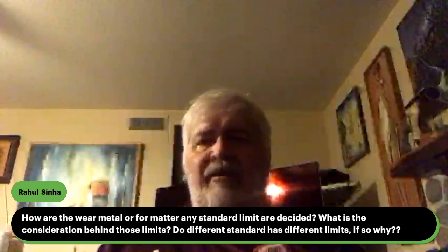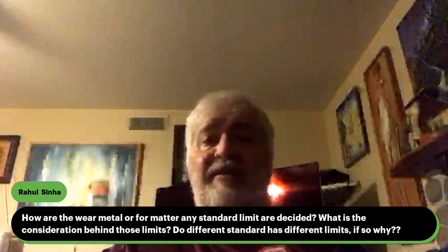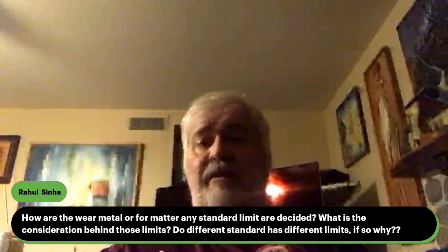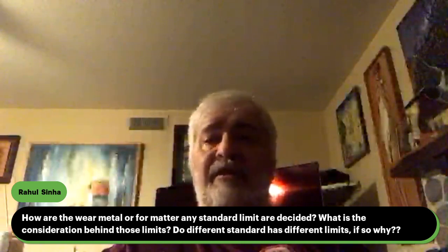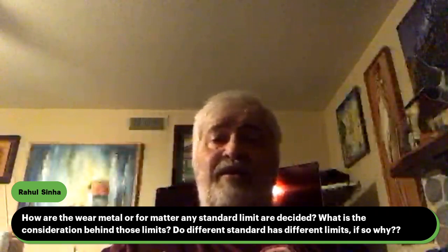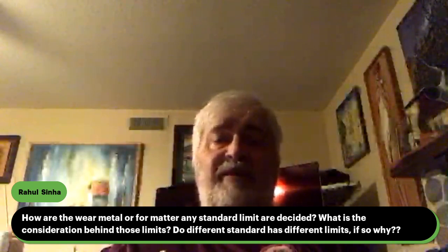So in terms of the wear metals, they are actually a little bit easier because you can go get a national standard, and the national standard would be basically for that type of instrument, dissolved metals that are carefully measured and blended and vetted by a national organization, and that is accepted as a known value. So those are actually pretty easy. We can buy the standard. It comes with the certification, and we can use that on our instrument. We can see how we're doing against the standard. A little more difficult if we don't have a national standard to anchor to.